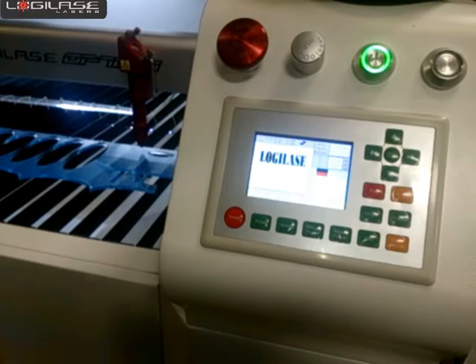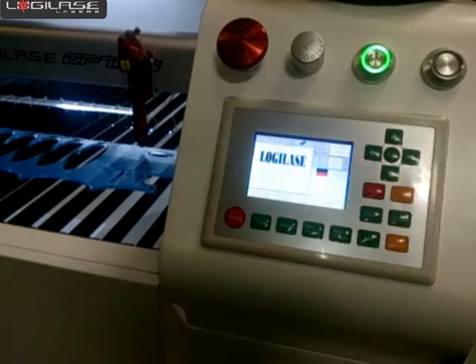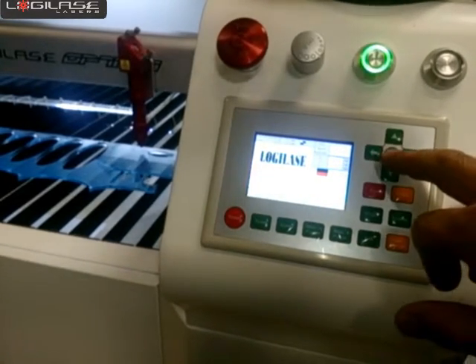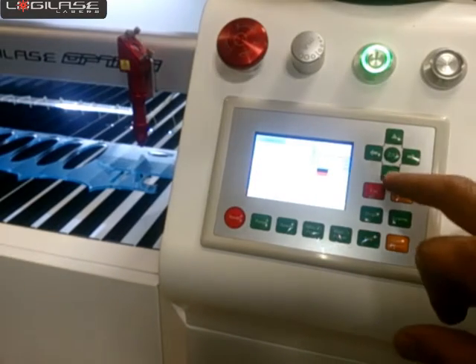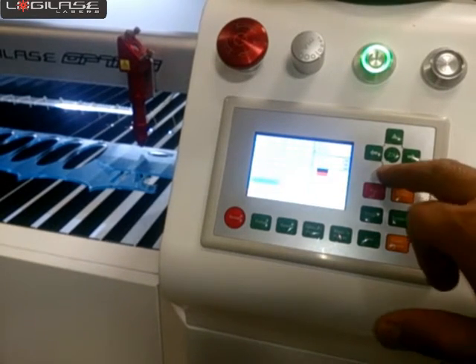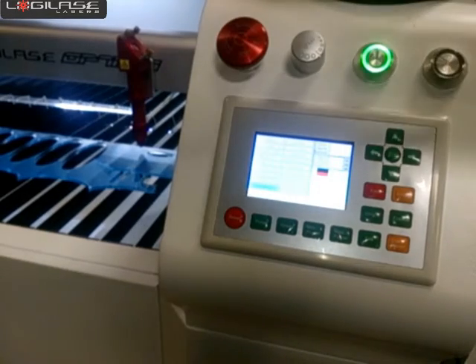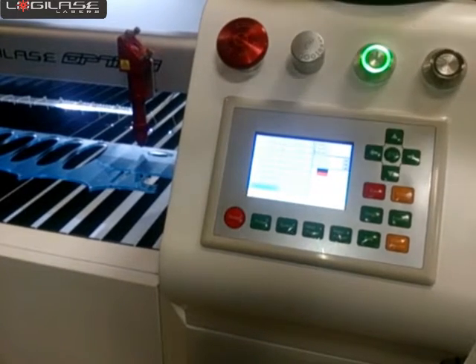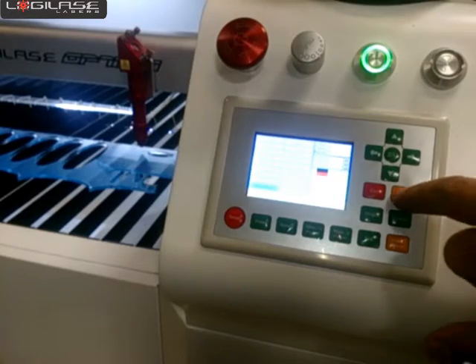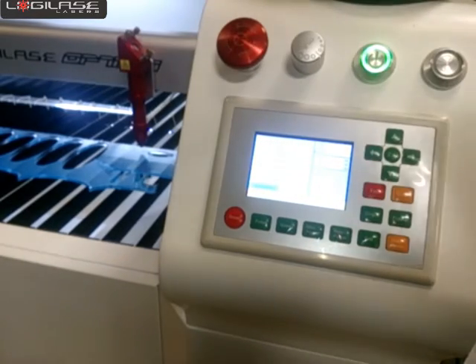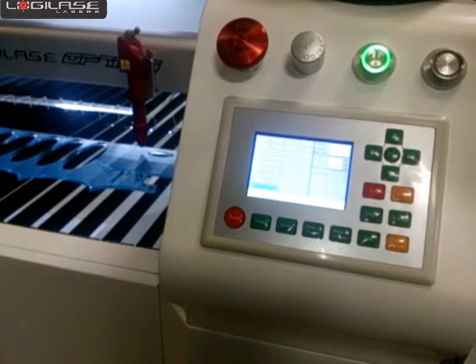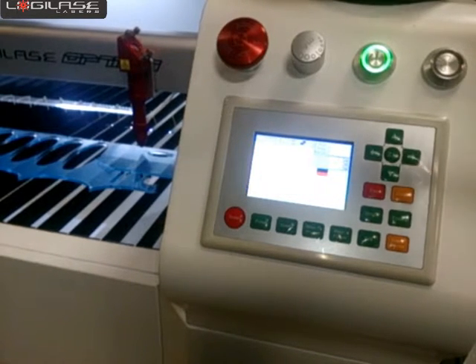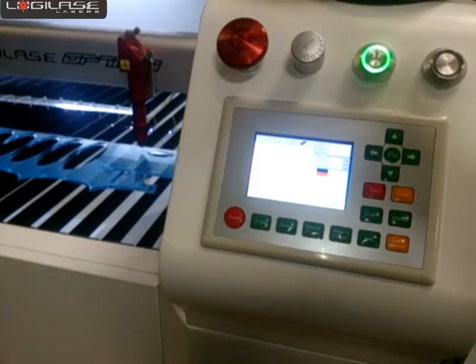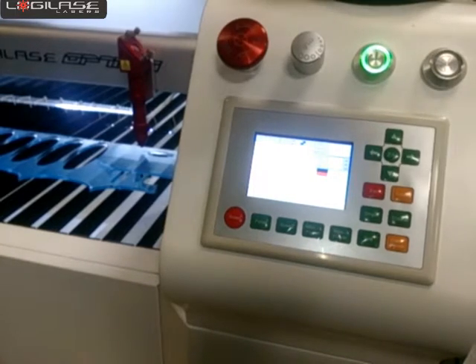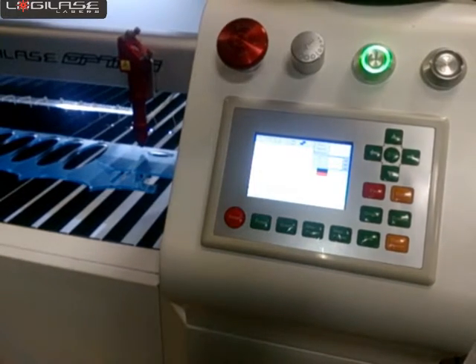If you have a machine equipped with an autofocus, you just press the Z button and then move to autofocus. Make sure the material is underneath the autofocus probe and press enter, and the table starts moving up, touching the autofocus probe and going back. This particular machine doesn't have autofocus, but this is the way you do the autofocus process.